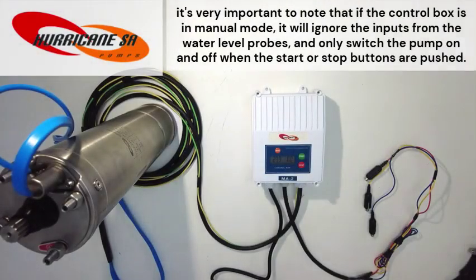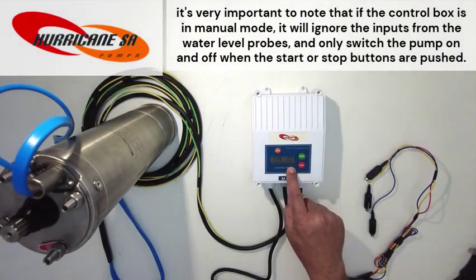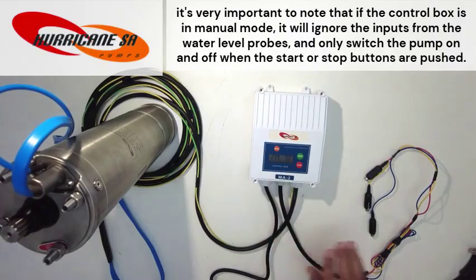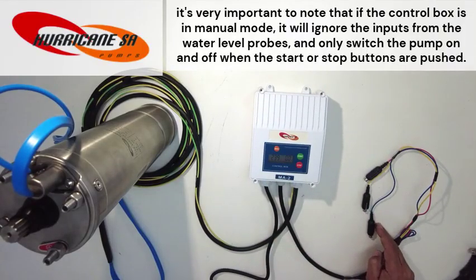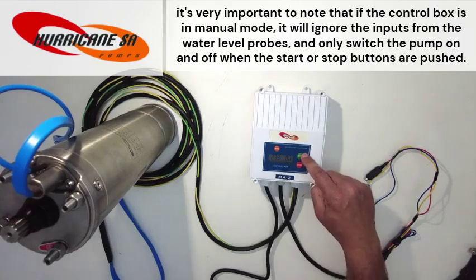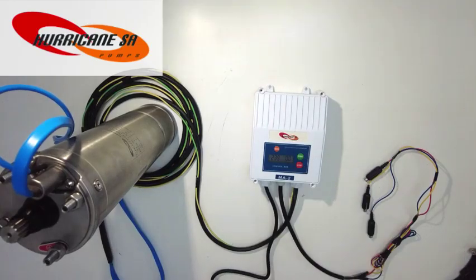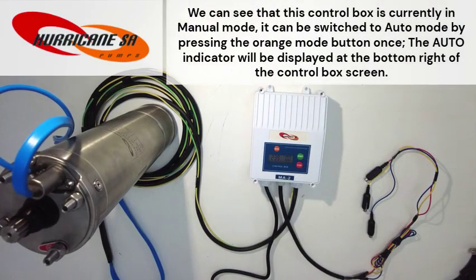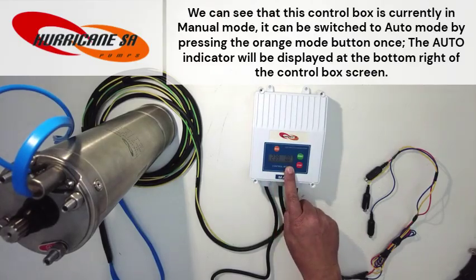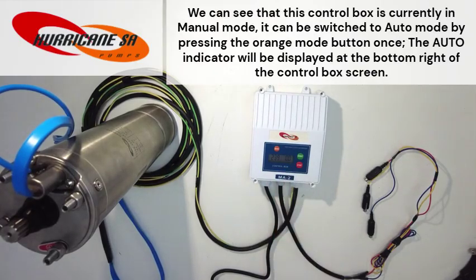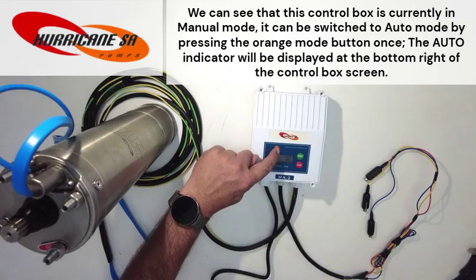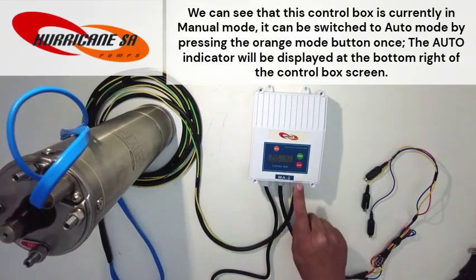It's very important to note that if the control box is in manual mode, it will ignore the inputs from the water level probes and only switch the pump on and off when the start or stop buttons are pushed. We can see that this control box is currently in manual mode. It can be switched to auto mode by pressing the orange mode button once. The auto indicator will be displayed at the bottom right of the control box screen.